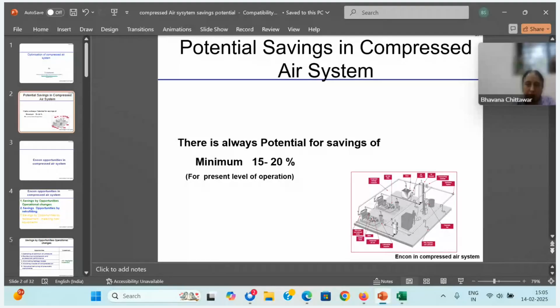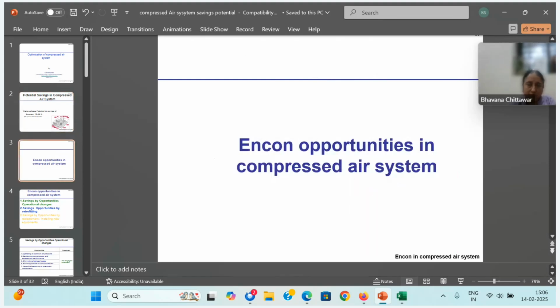You cannot see the compressor system in isolation. If you see it in isolation, you will get savings of only 3 or 5%. But if you properly audit or investigate the total system, you can achieve greater results. So I'm calling these opportunities in compressor systems. I will quickly go through what opportunities are available, even though they are covered by other speakers. Then I'll come to some special projects.